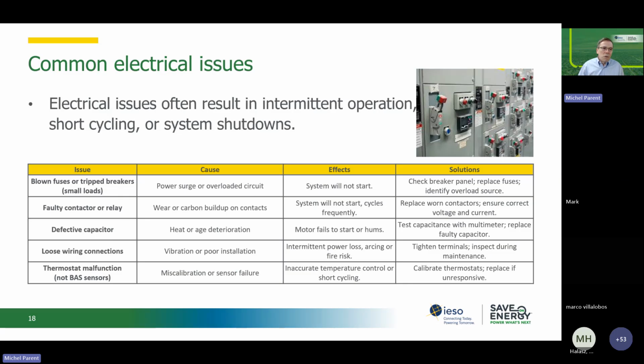So the most common issues will be, actually, I'm going to go past the blown fuses and tripped breakers, because that would be a very, very small load. I'll get back to that. But when you have electrical issues, it will very often be a motor not starting. And if it's on the electrical side that the motor is not starting, because it could be on the control side, obviously, very often it will be related to the starter, with the capacitors that are part of there, because capacitors do age and deteriorate, and contactors, especially if you've got short cycling with a motor that starts and stops all the time, it gets really hard on the contactor or the relays, and they will actually eventually fail.